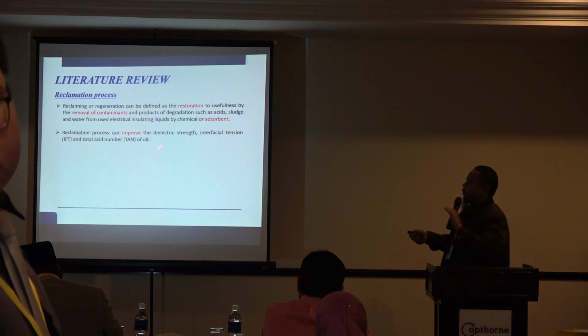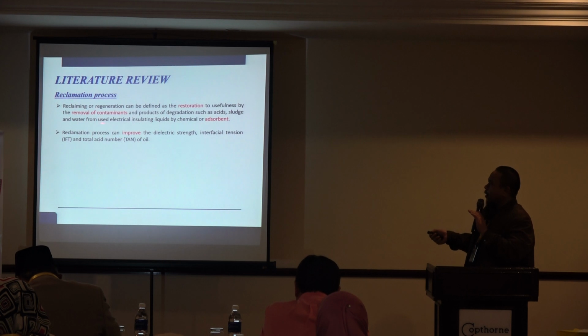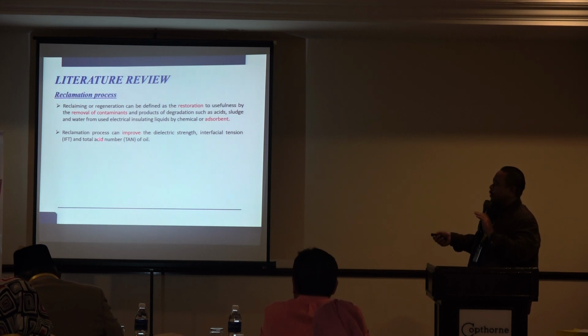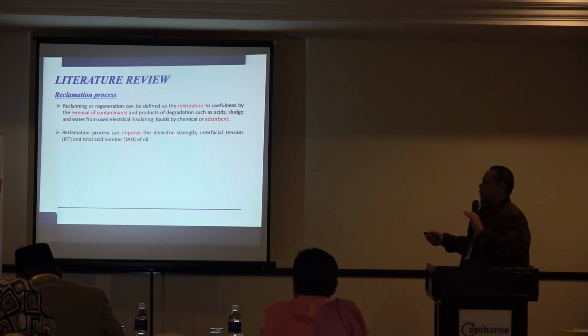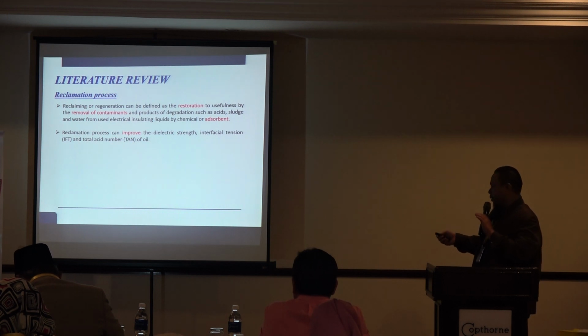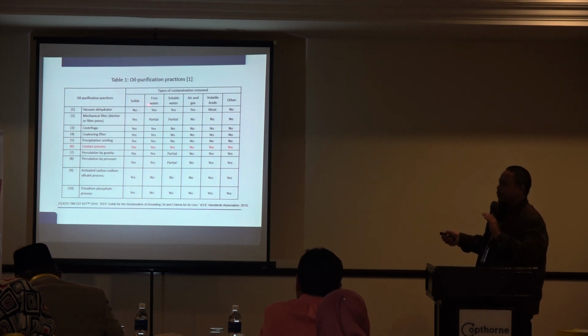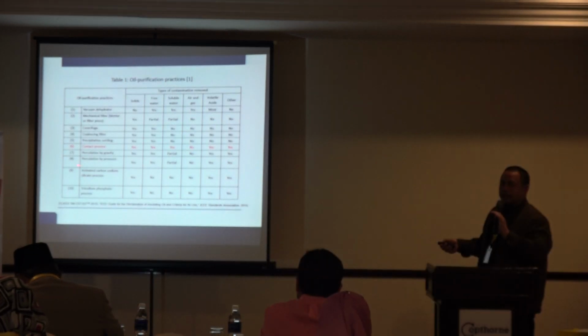So how does the reclamation process work? We apply fuller's earth inside the transformer oil, do the reclamation, and then see whether we can improve the dielectric strength of the insulating oil, the interfacial tension, or the total acid number of the oil. This is a review of the purification practices or reclamation processes. There are ten practices, such as vacuum dehydrator, mechanical filter, contact process, by gravity, and so on. Here we are dealing with the contact process, which means mechanical agitation of the oil with the fuller's earth.